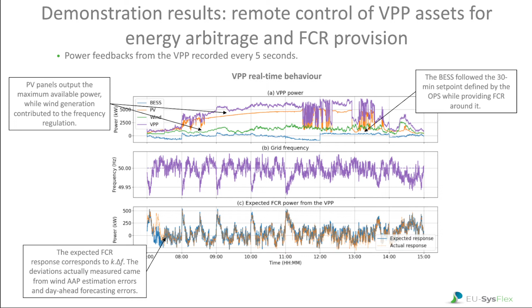Here on this slide, the real-time behavior of the VPP is shown. The actual power of the VPP corresponds to the sum of the battery storage power and the power output by wind and PV generators. As programmed by the operational planning scheduler, the battery followed the 30-minute set point defined by the optimizer and provided FCR around its baseline operating point.